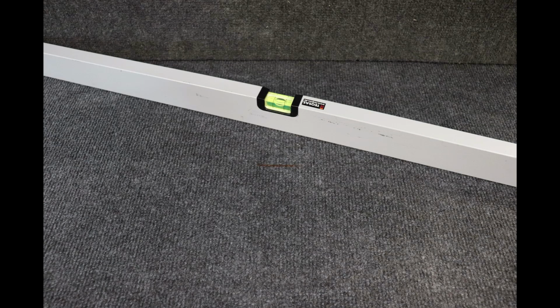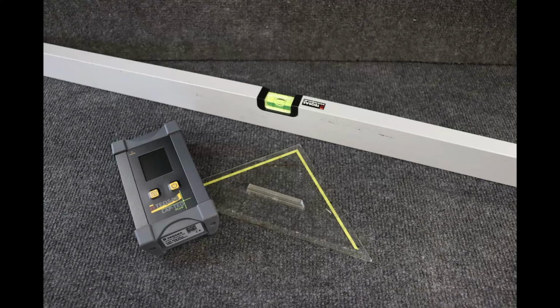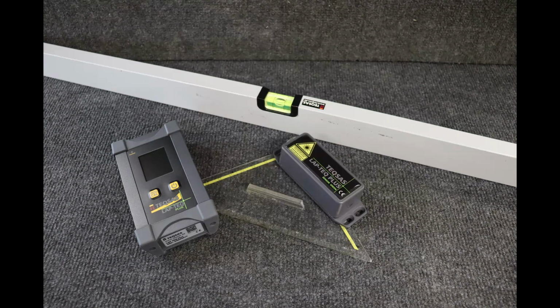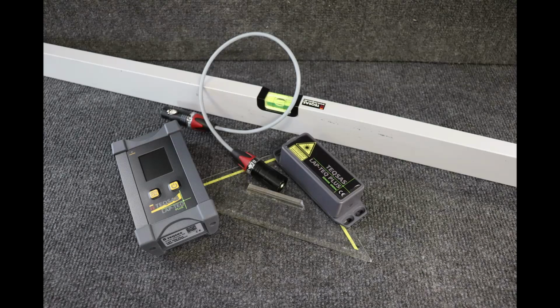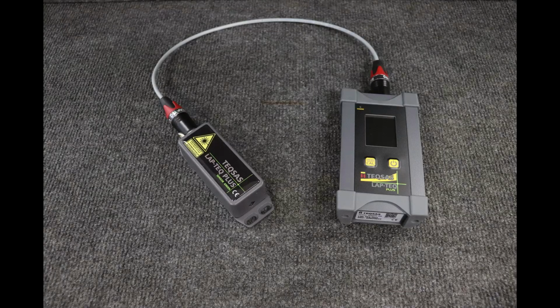For calibration, we need a spirit level, a ruler with 45 degrees angle, the Lap-TEQ Plus display, Lap-TEQ Plus sensor, and the special calibration cable that is included in the Lap-TEQ Plus set. Connect the sensor and the display using the calibration cable. Use the spirit level to verify that your table or work surface is leveled.